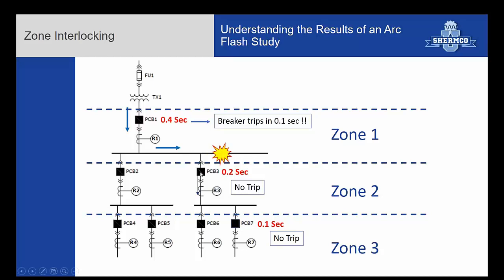You can zone interlock from your feeder breakers in your gear down to panels. Same thing, if you zone interlock, one of these two breakers would need to send this breaker a signal if the fault was downstream. So once you get outside of the switchgear, what we've seen is it becomes pretty unreliable. It can be done. I've seen successful installations, but you really have to make sure that your distance doesn't get too far because you're really dealing with a low voltage signal. So zone interlocking, I think, is a pretty good way to reduce arc flash on your main bus in your switchgear lineups. Going downstream of that, I think you need to really consider distance and then decide, is the reliability worth the benefit that it gives you.